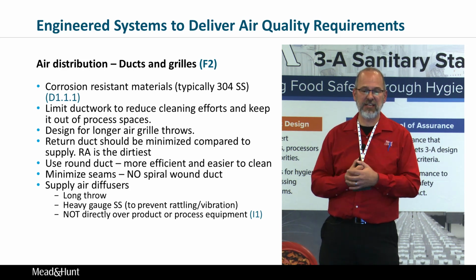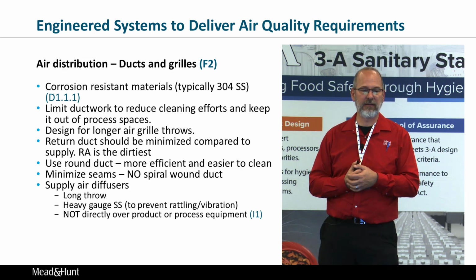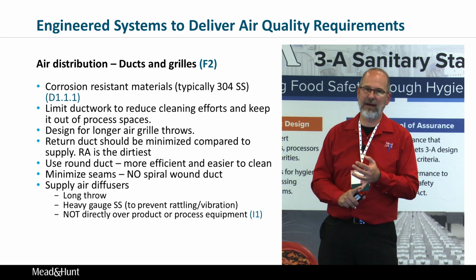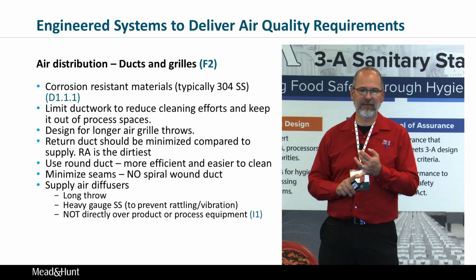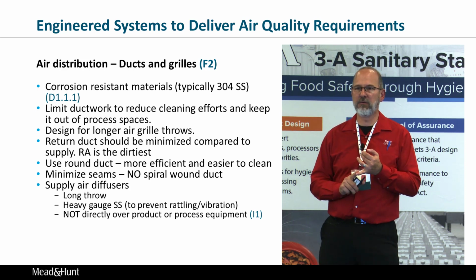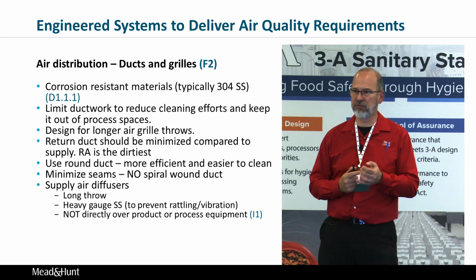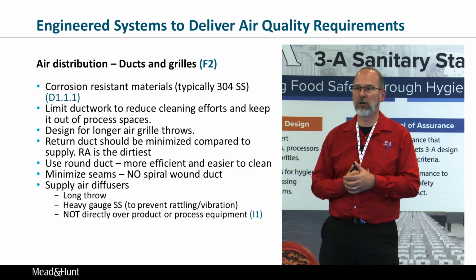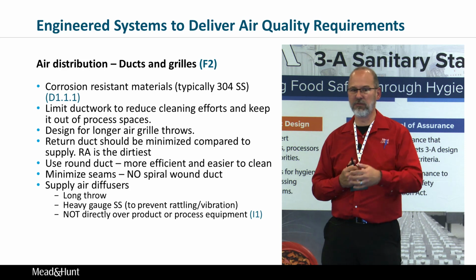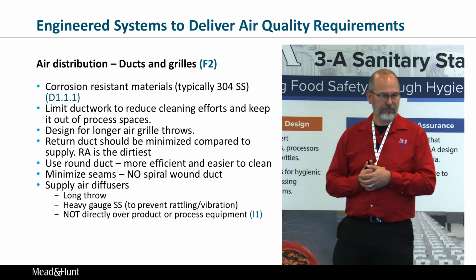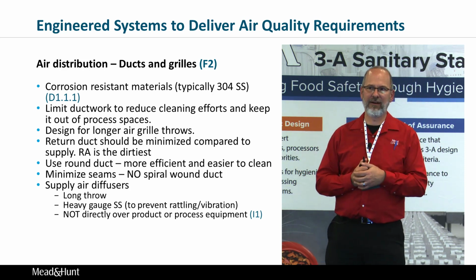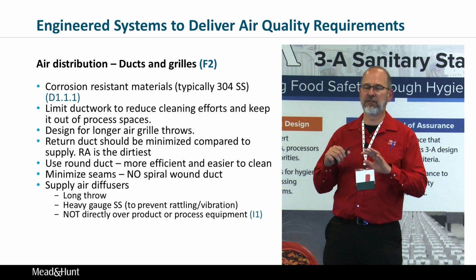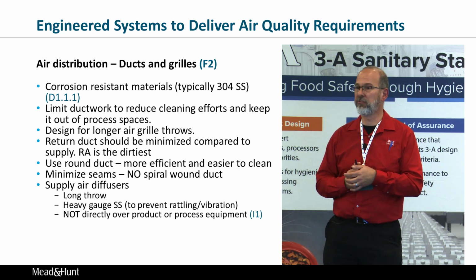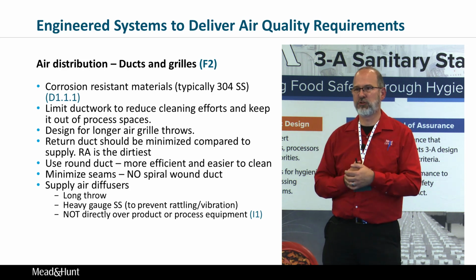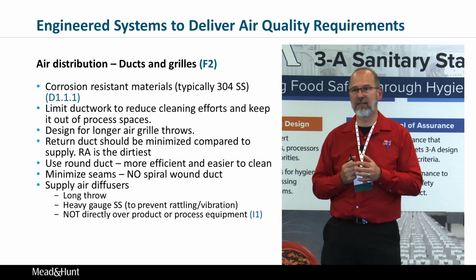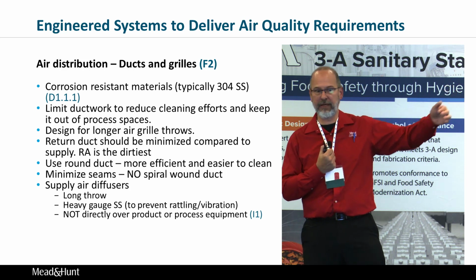And one of the ways we achieve that is by designing the ductwork for higher velocities and longer throw. We're not concerned about noise in a food plant the way HVAC designers are in a commercial facility. So you can design the ductwork a little smaller so that air is screaming when it goes through there. So the return air ductwork on an air handler, the air coming back from the process room to the air handler, is typically the dirtiest air that the duct system will see. So I like to make that the shortest section of ductwork possible. If that means making the supply section longer, that's okay.